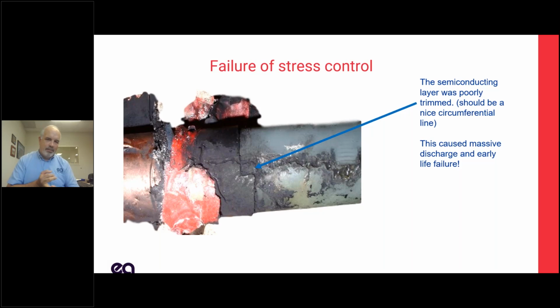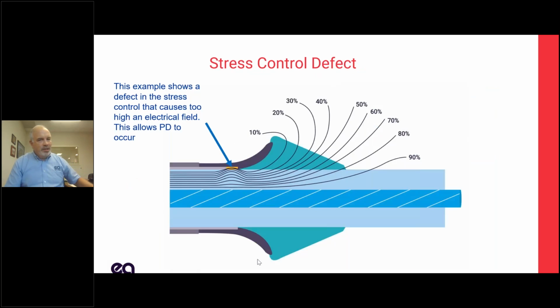There was likely a gap, because the parts that go over this are not designed to fill that sort of opening. And so you got discharge, and you can see the discharge tracked in both directions until eventually it made a nice conductive path from the shield to the conductor, and it failed catastrophically. This is typical. It happens every day somewhere in the world. A cable's failing. It's not the fault of anyone except those who are managing the installation.